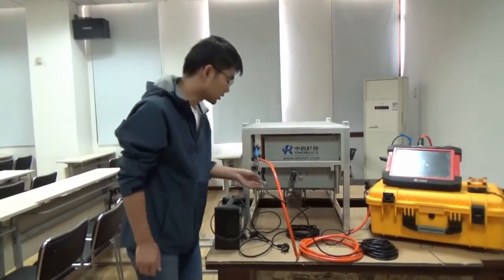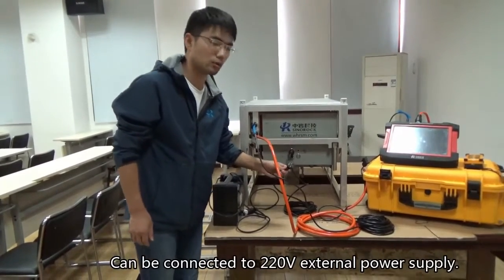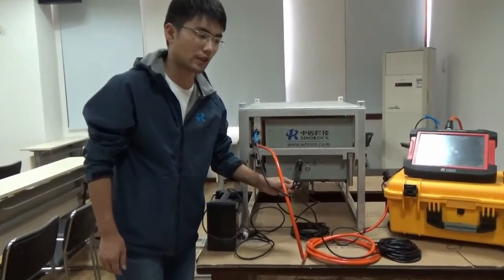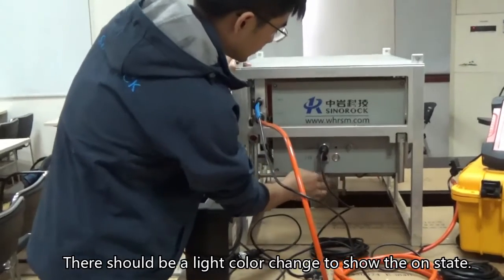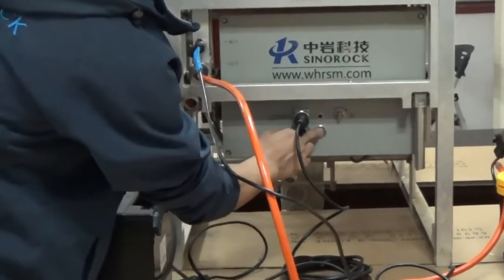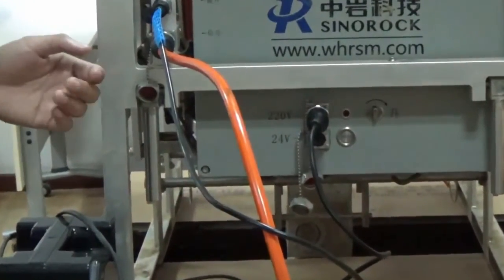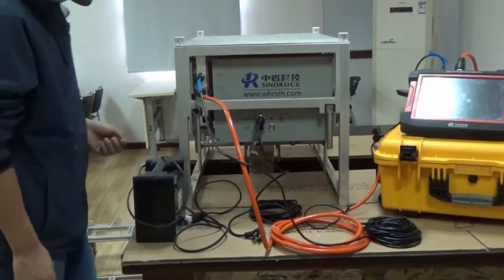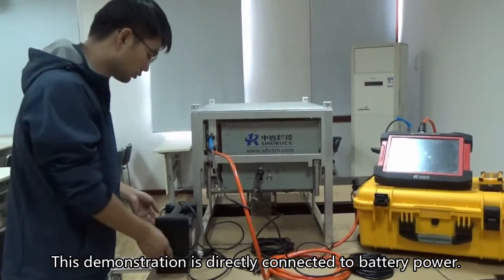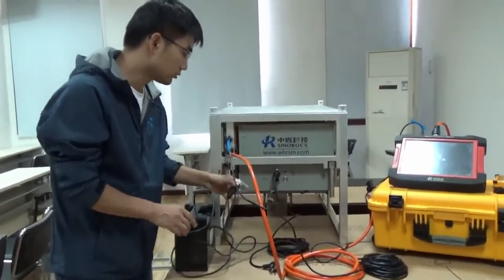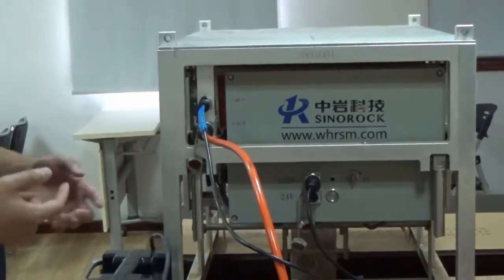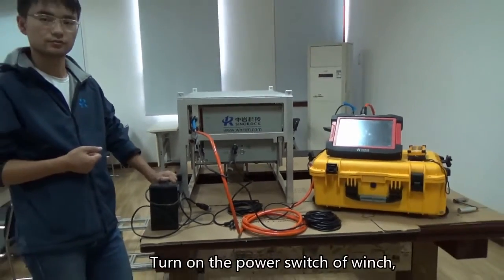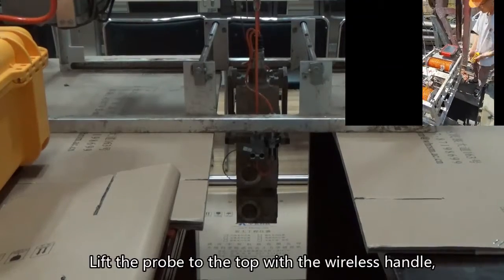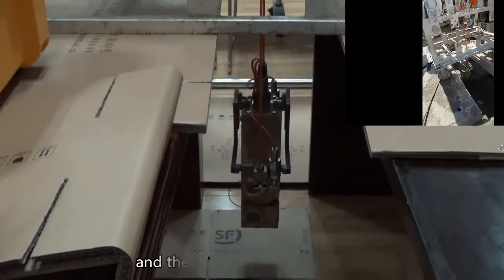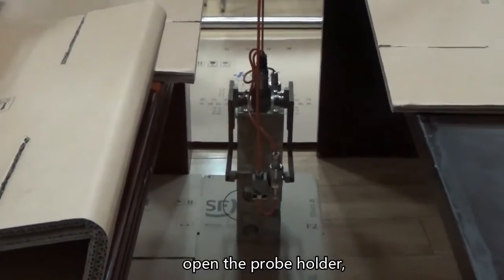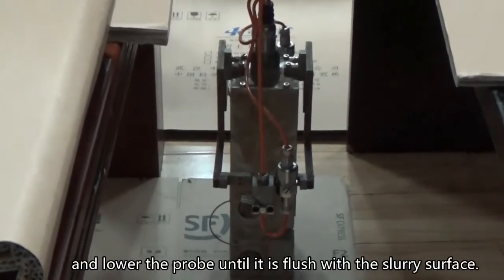Connect the power supply. Can be connected to 220V external power supply. There should be a light color change to show the on state. This demonstration is directly connected to battery power. Turn on the power switch of winch. Lift the probe to the top with the wireless handle. And the probe will stop automatically. Open the probe holder. And lower the probe until it is flush with the slurry surface.